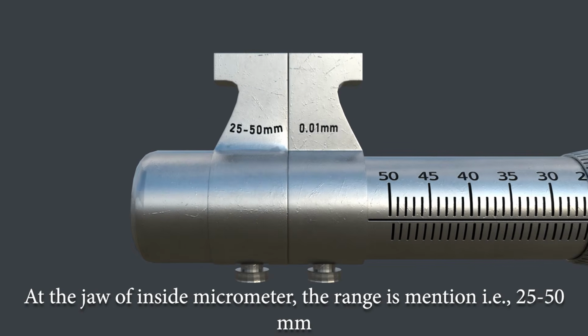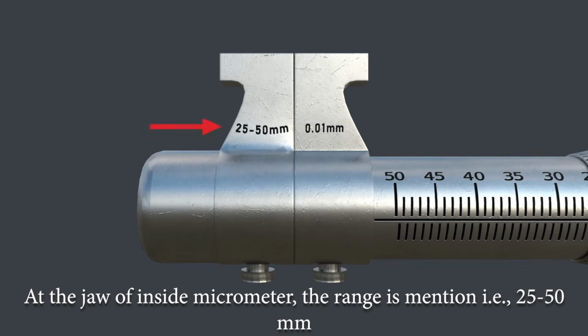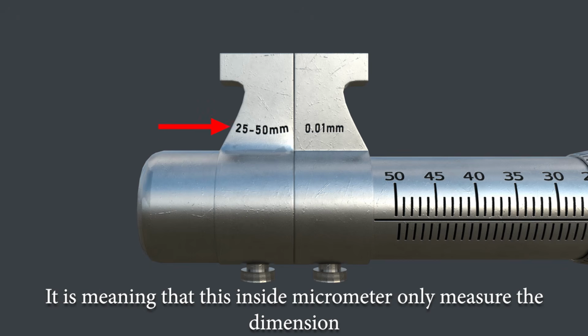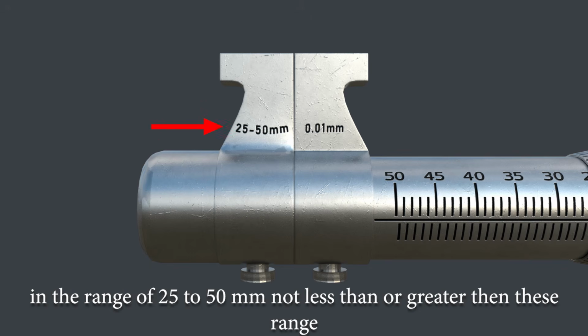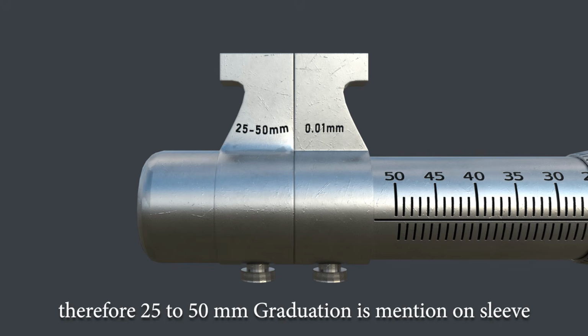At the jaw of the inside micrometer, the range is mentioned, that is 25 to 50 mm. It means that this inside micrometer only measures dimensions in the range of 25 to 50 mm, not less than or greater than this range. Therefore, 25 to 50 mm graduation is mentioned on the sleeve.